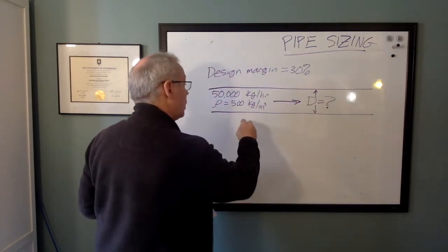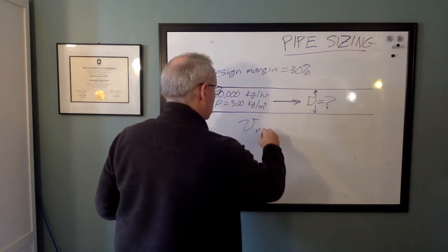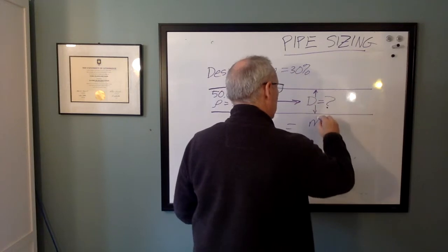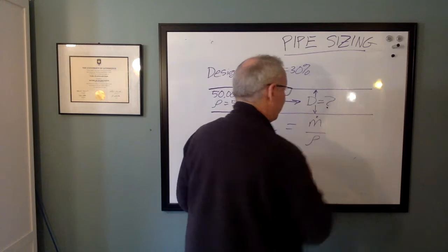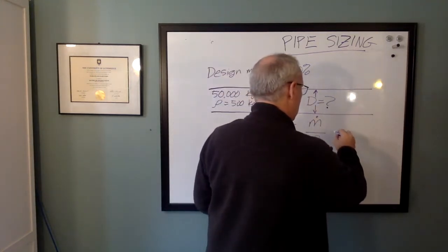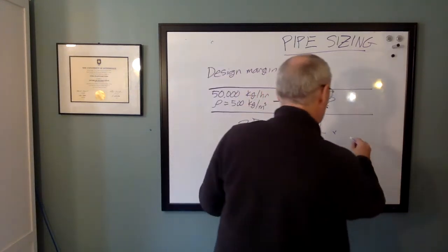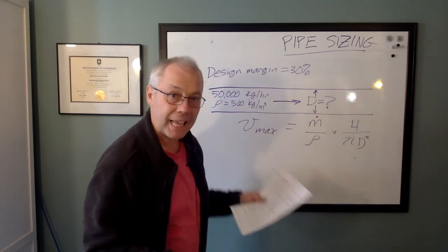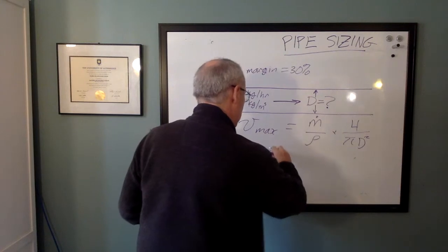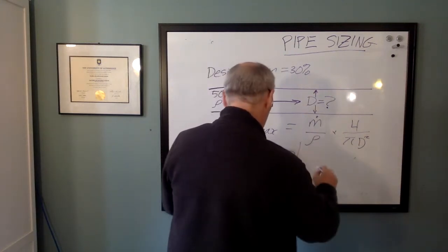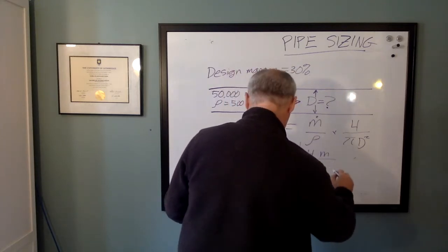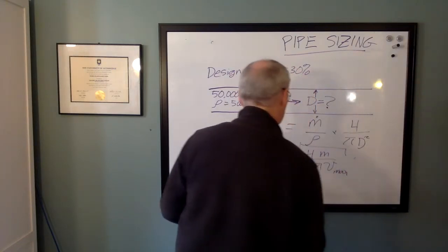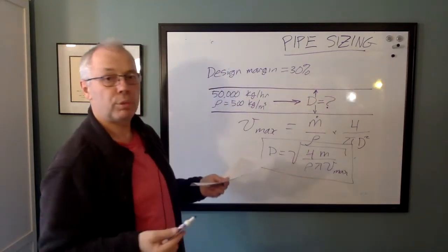So we could say the maximum velocity that we can tolerate is equal to whatever the mass flow is through our pipe. We'll divide that by fluid density so we get a volumetric flow rate. And now we'll divide that by the inside area of the pipe. And that's pi d squared, and we'll stick the four up there. And that's how we get it. And we can write this as an equation for diameter. We can say d is equal to the square root of 4 times mass flow rate over rho pi v max. And there is a perfectly good formula for sizing the pipe.